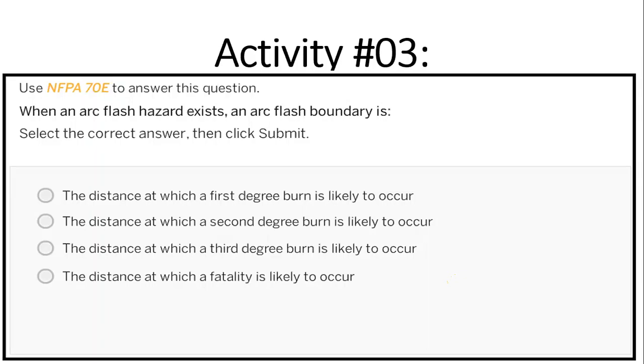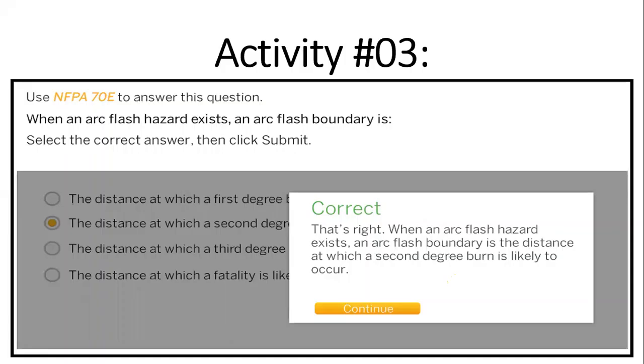NFPA defined that this boundary should be made up to the point from the energized equipment where there is a chance of second degree burn. Meaning that if an arc flash event occurs at energized equipment and the incident energy goes up to 10 meters and causes a second degree burn at 10 meters, draw the boundary there. Keep your unqualified persons beyond that 10 meters and allow only qualified persons to enter within it, with all their PPE intact. So the second degree burn distance is where you make the arc flash boundary.